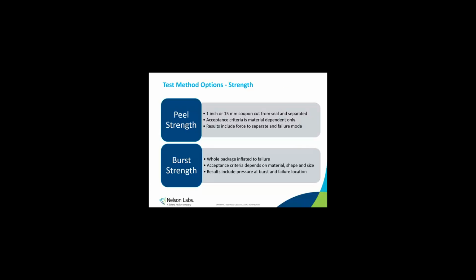After distribution, we need to test the sterile barrier system for those 3 attributes. Let's start with the strength testing. The strength component ensures that the package is sufficiently sealed to remain sealed and thus sterile until intentionally opened. The 2 most popular options are seal peel and burst. Both these tests generate variable data or a numerical value, and for both, you need a minimum value as the acceptance criteria. The strength minimum should be a value that's within the expected sealing capacity of the materials, and it needs to be sufficient to keep the package closed until the point of use.